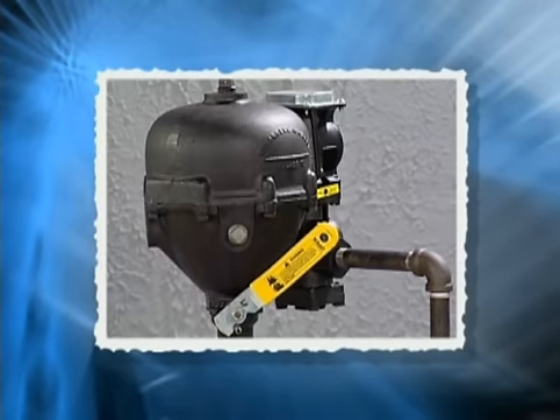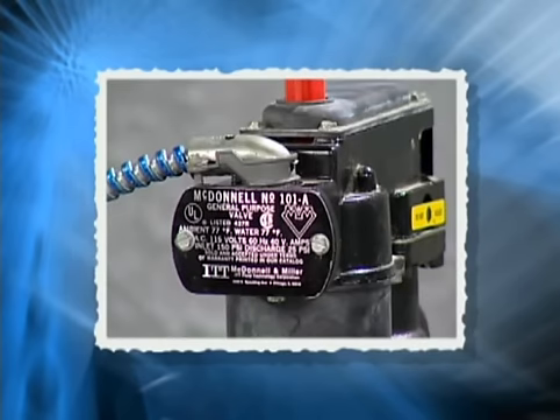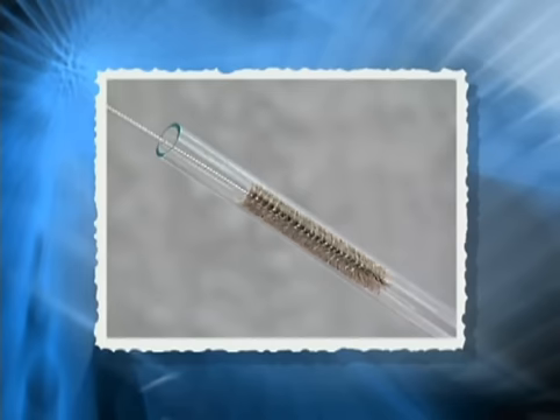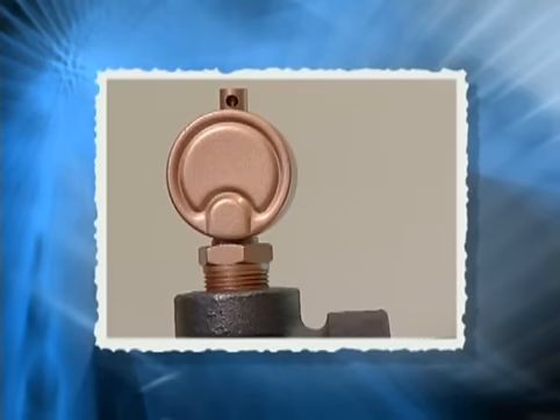Check the low water cutoff by blowing it down and draining water from the system until the burner shuts off. Check the automatic water feeder. Check the sight glass and replace it and the washers if necessary. If the glass fills with dirty, oily water, skim the boiler until it clears up. Check the main vents. Look for evidence of water leaks.